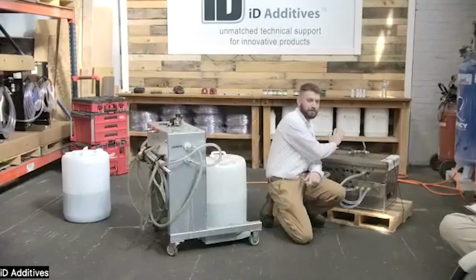In order to keep your chemical at peak performance, we want to filter out all the contaminants that it's pulling out, right? The active ingredient in there wants to break down calcium, silica, manganese, fresh iron, not hardened iron. But that's what the filter's for. It wants to capture it before it gets back into the drum, because if it makes it back into the drum and it sits there, obviously that active ingredient wants to just keep attacking and eventually it'll lose effectiveness.